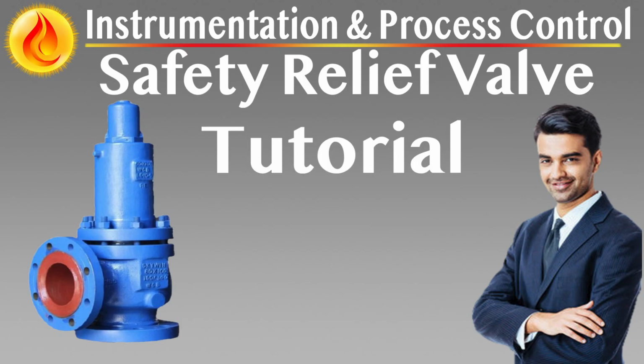Bellows design and safety features. The metal bellows assembly compensates for the effect of back pressure on the disc. The bonnet is vented continuously to atmosphere or to a safe area to prevent pressure buildup behind the bellows and to provide an escape path for process fluid in case of bellows failure. Bonnet vent lines must be routed to a safe location, protected from ingress, freezing, or blockage.